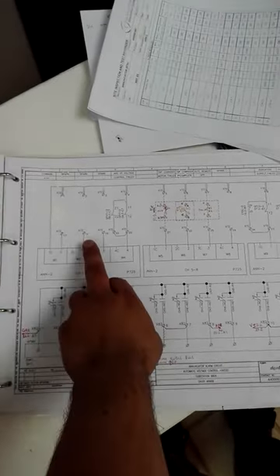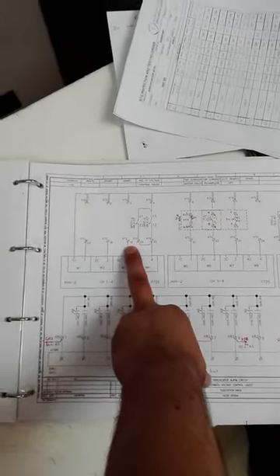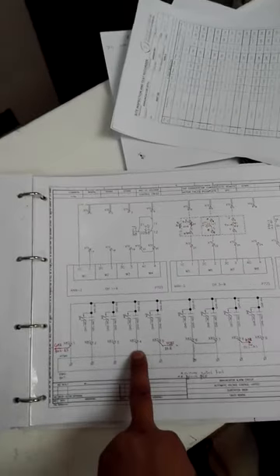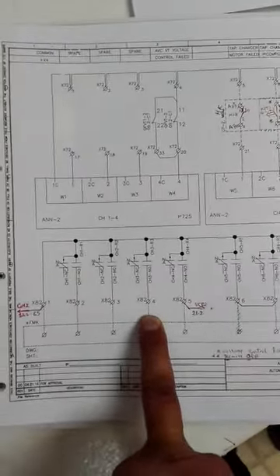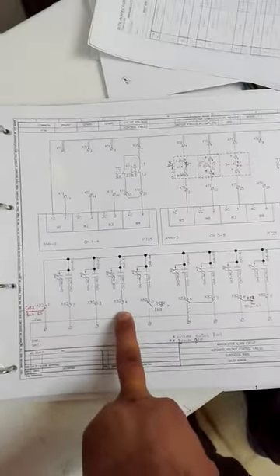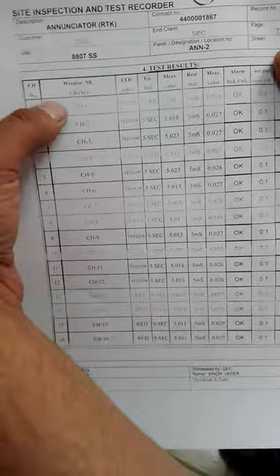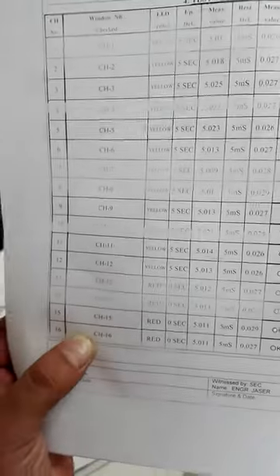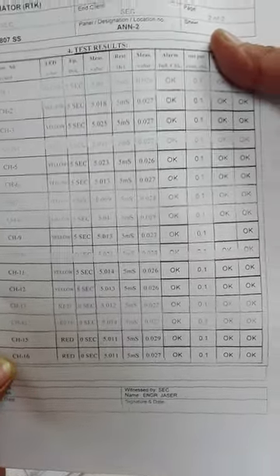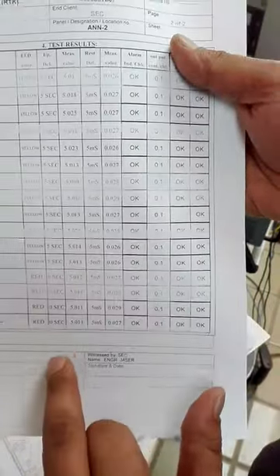Now we will move from point 18 to point 19 of our terminal block X72. Okay, and the same pattern will be followed. Here we will move to X82.4 and we will measure the time and the delay to come to its normal position, and we have the final table for you. You can see it labeling the channels, channel 1 up to channel 16, because in this AVC panel we are using 16 channels, and this is the 5 seconds for the whole arrangement, and then we measure the time.